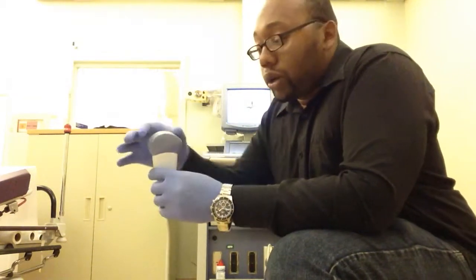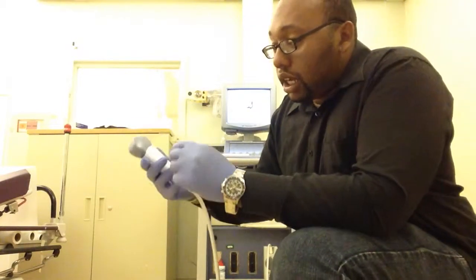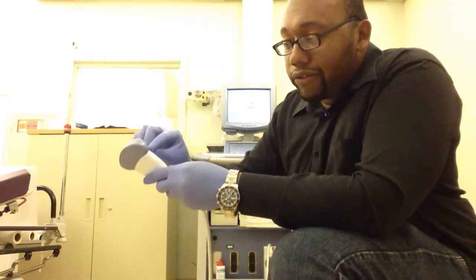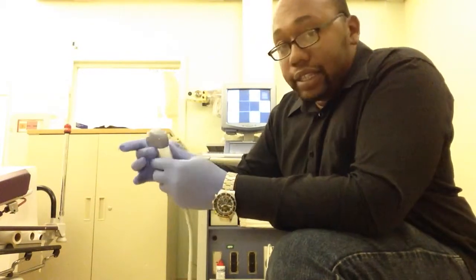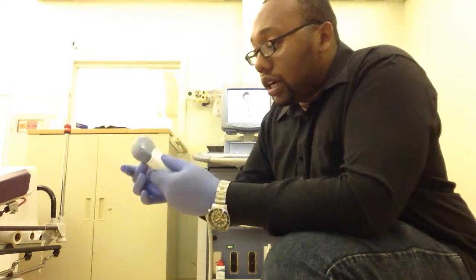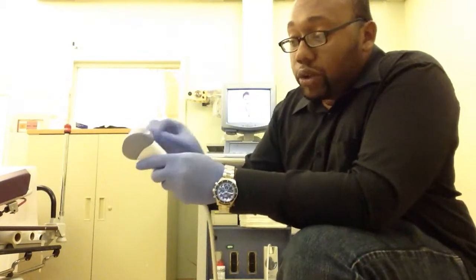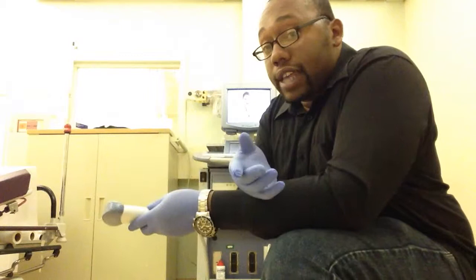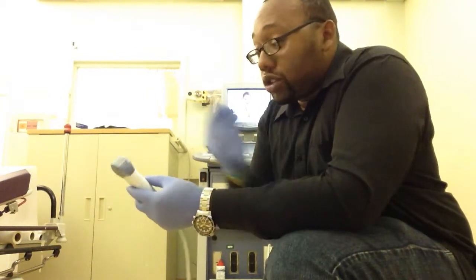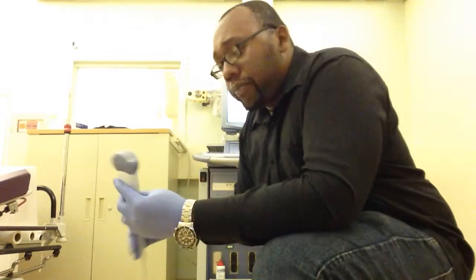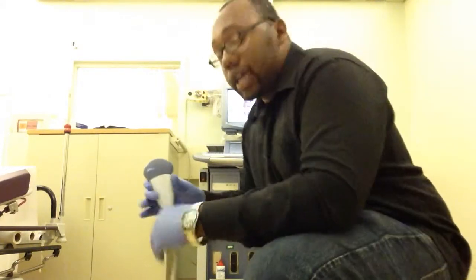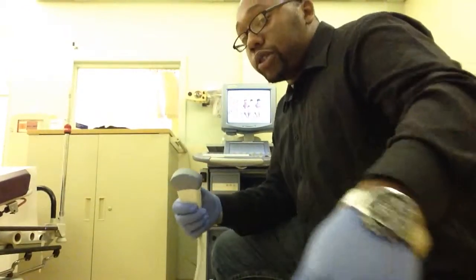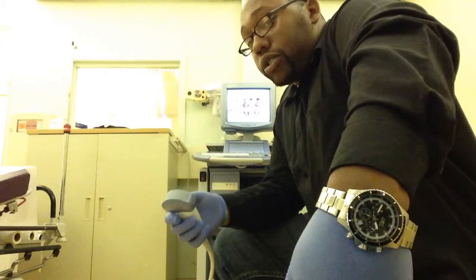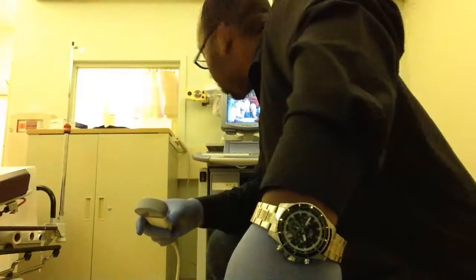Okay, so you want to make sure there's no swelling, no cracks. Make sure that this head is not detaching from the base, because that can be a problem. What occurs a lot of times too is when the head is detaching, you actually get moisture down in there. It can create an electrical hazard for the patient and for yourself. Okay, so you want to make sure that none of that is occurring. One of the main problems that a lot of ultrasound techs run into is that they're not getting a good image produced. Now, that could be a number of reasons too. One of the first things, when you first meet with that ultrasound tech, is to ask them a few questions and check a few things.